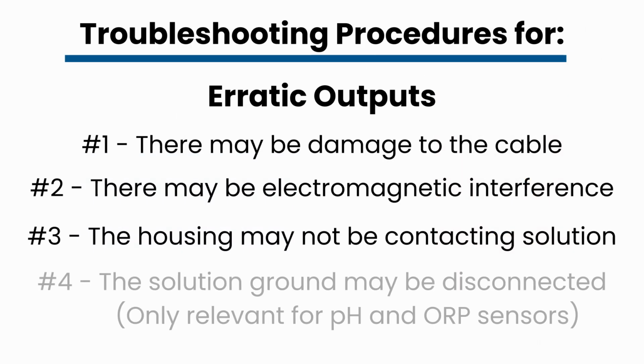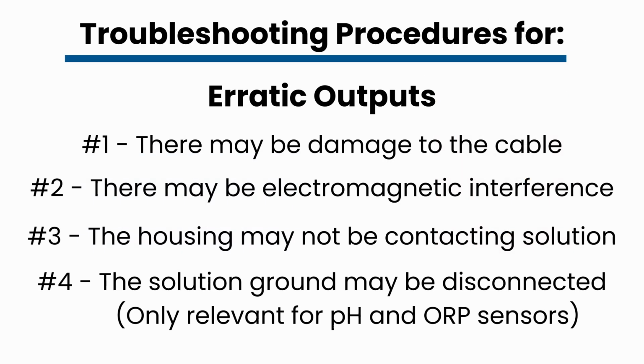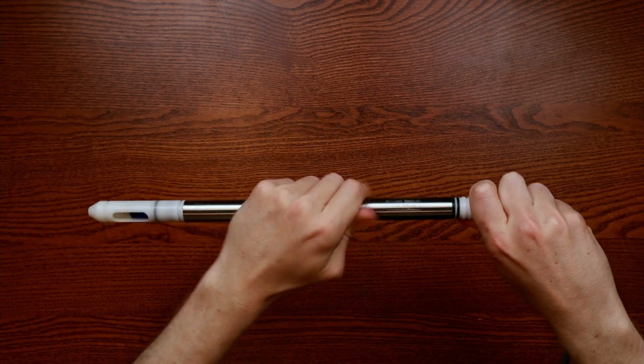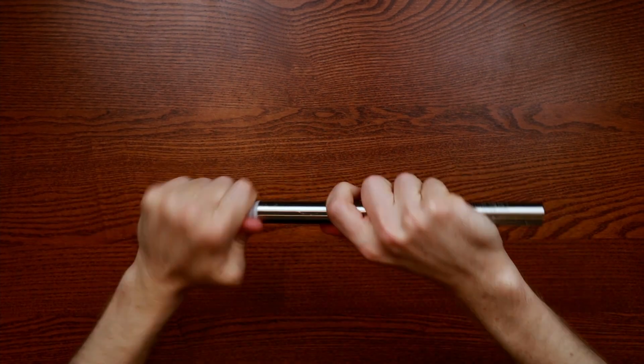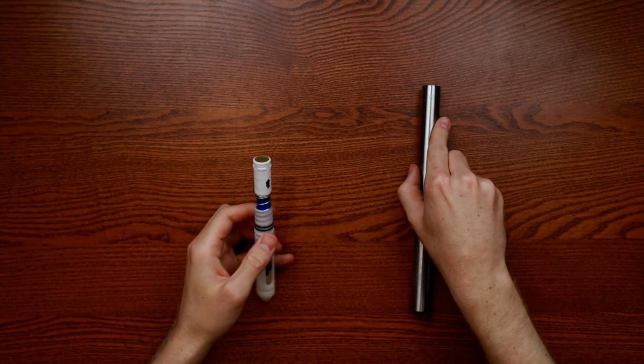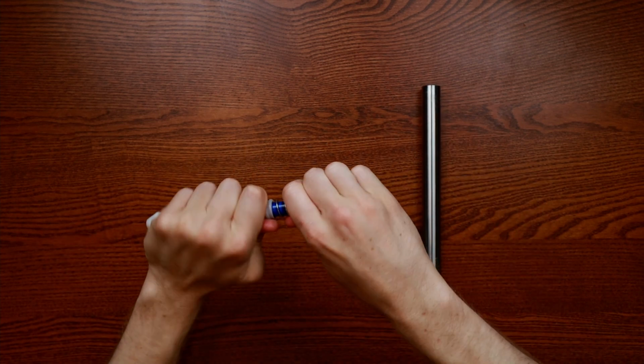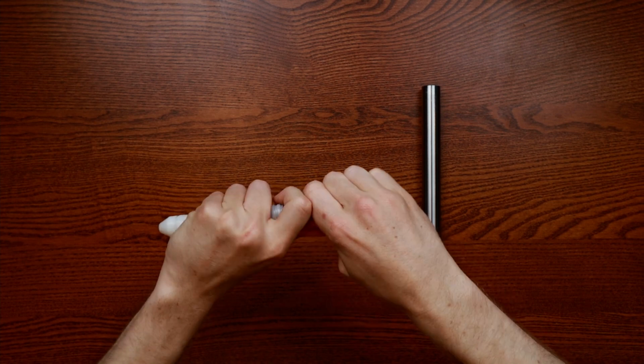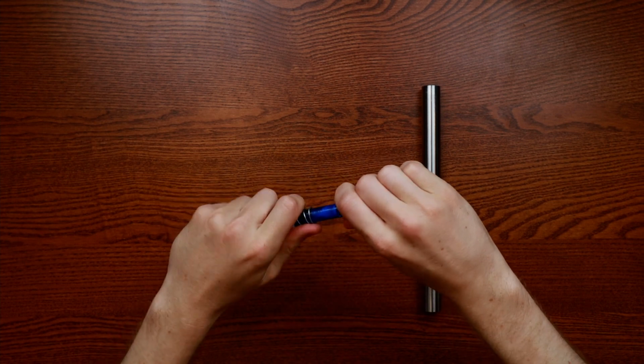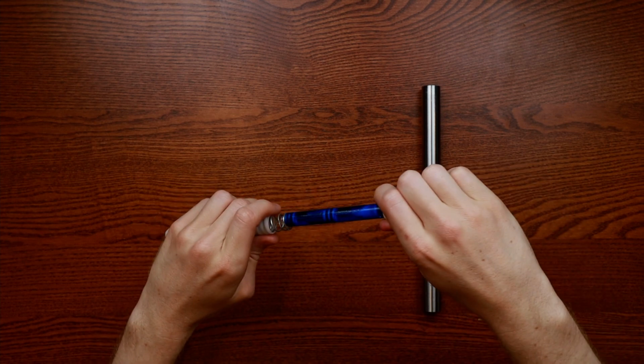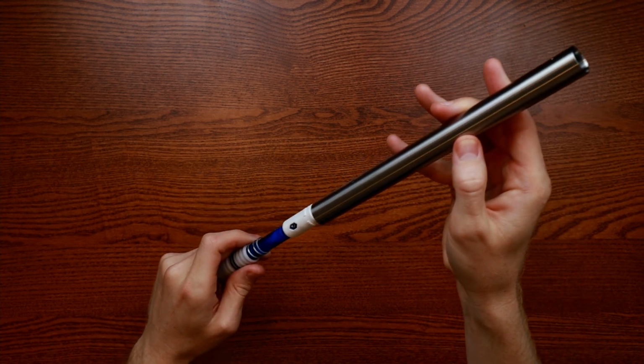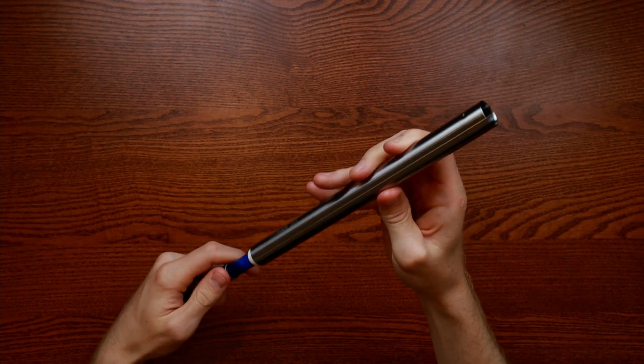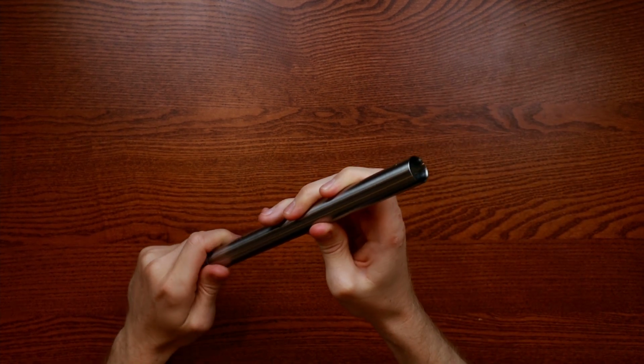Number 4. The solution ground wire inside the sensor may not be making solid contact with the housing. Start by removing the cable and electrode. Now we are going to use the electrode to push the circuit board out of the housing. To do this, pull the electrode out of the electrode body and lightly rest it inside, leaving the electrode extended.